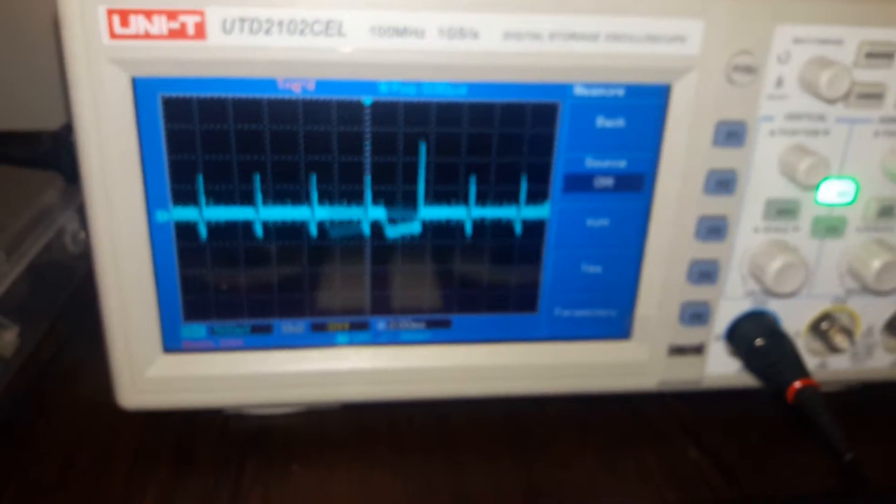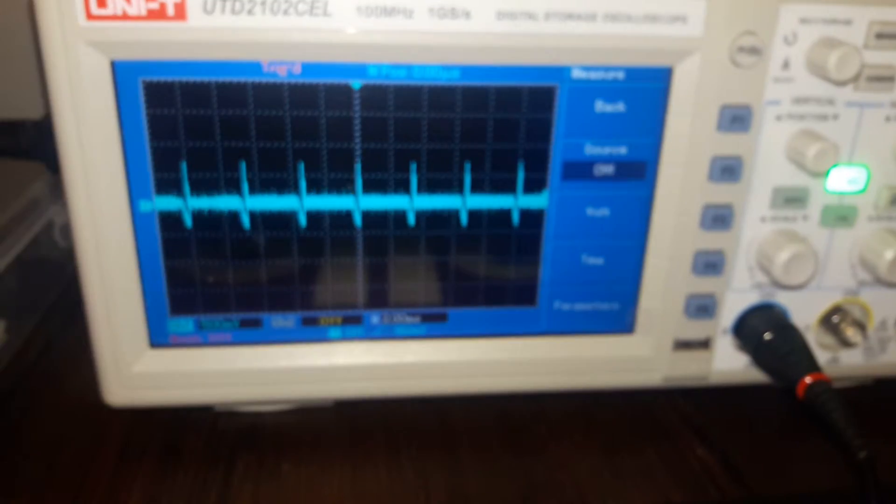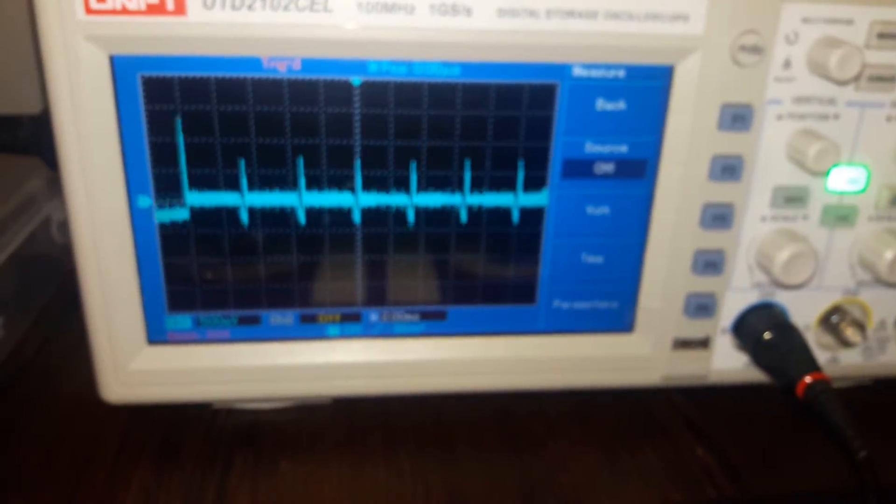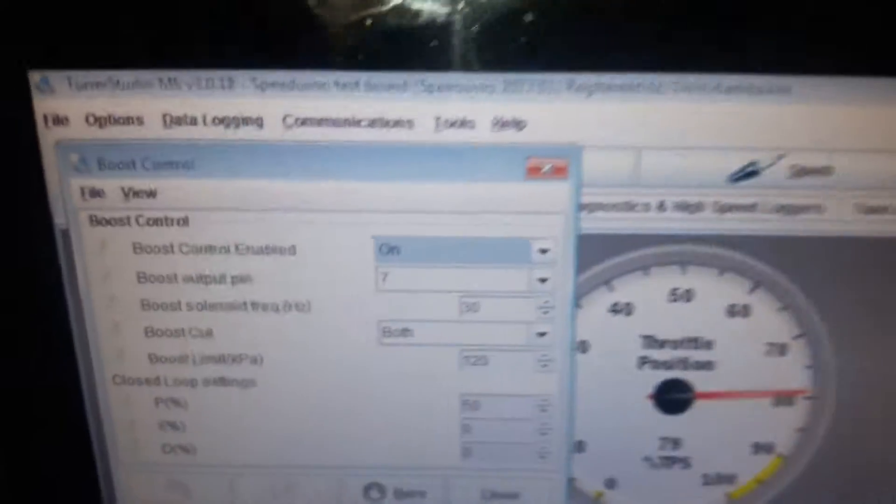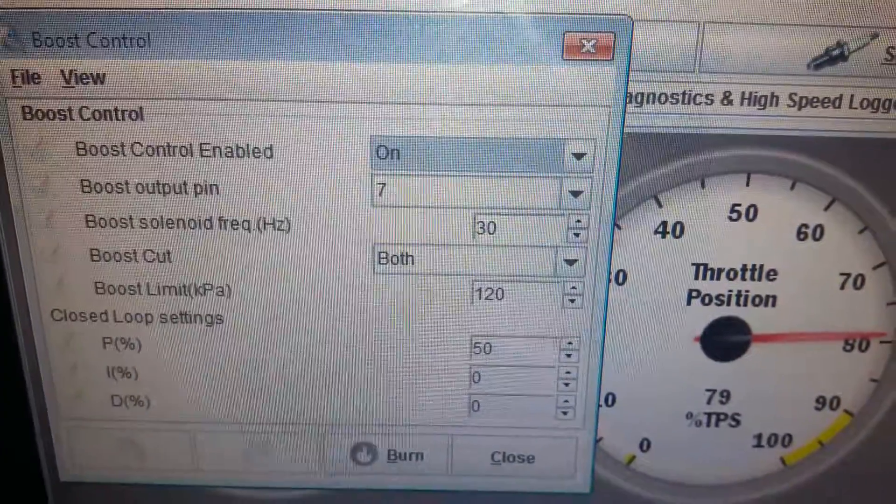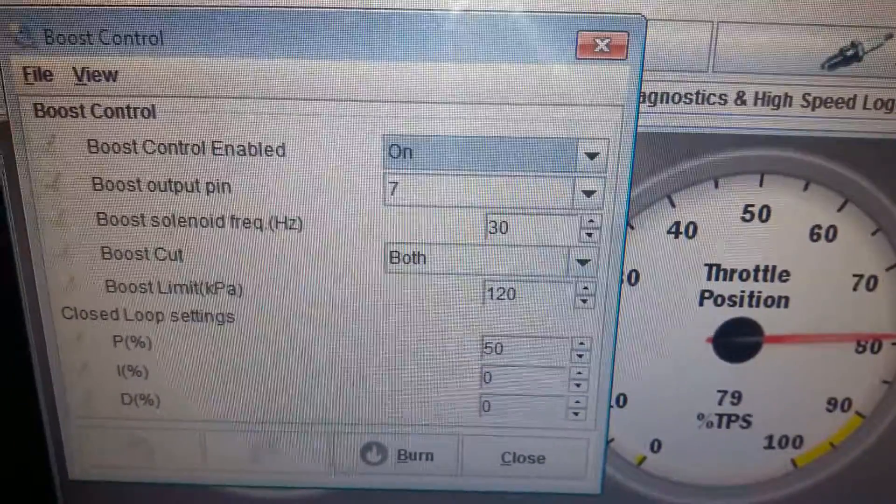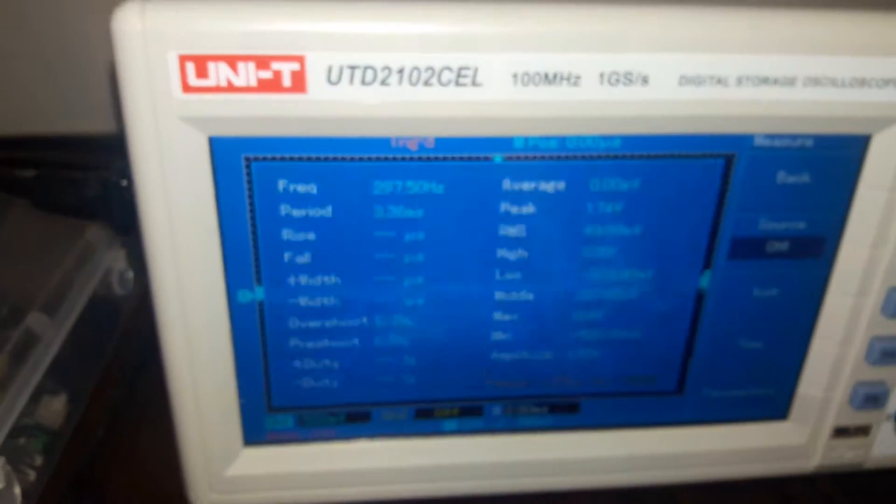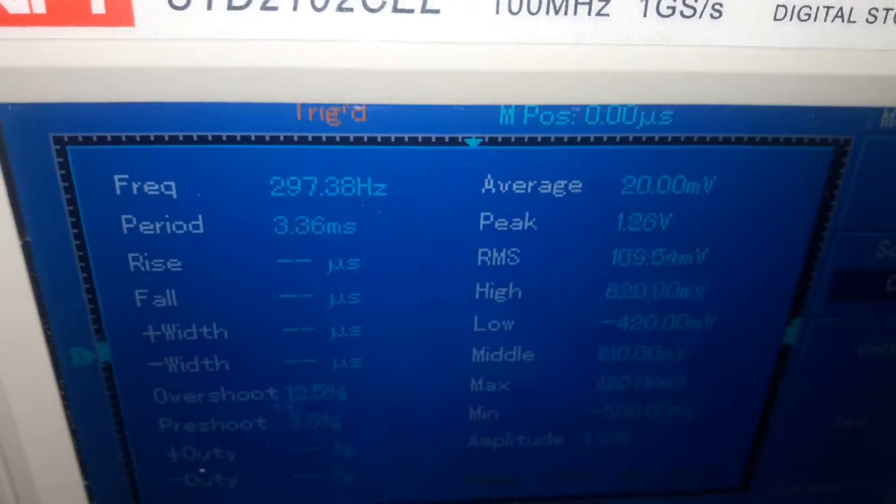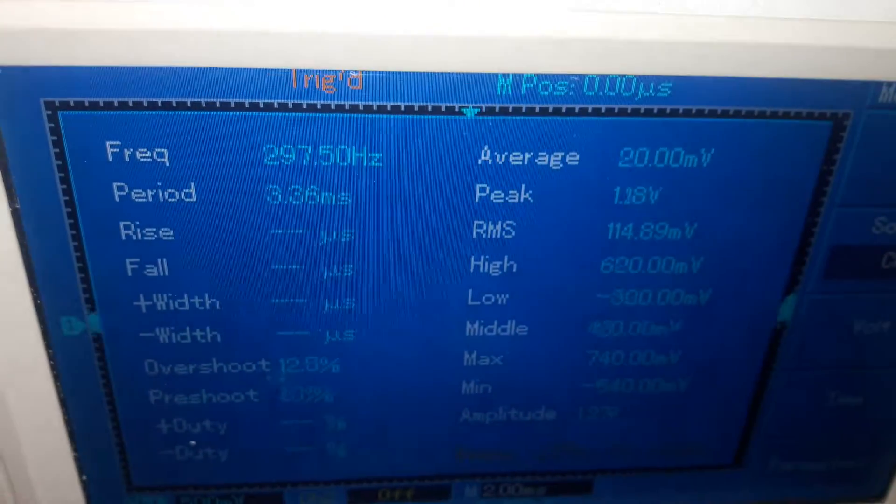Okay, so pin 7 now. Let's go and have a look at the settings. Right, we've got pin 7 and 30 hertz. Let's verify if we have in fact 30 hertz. We do not, right?